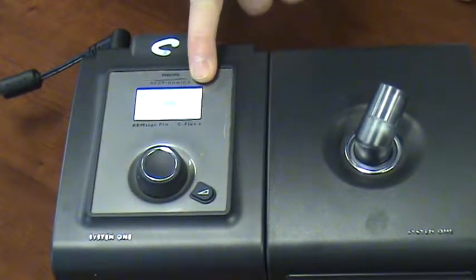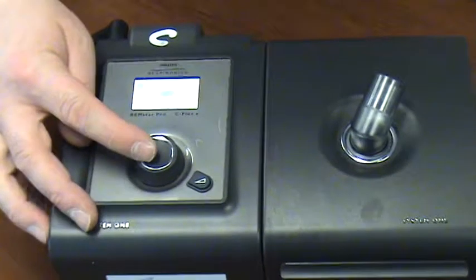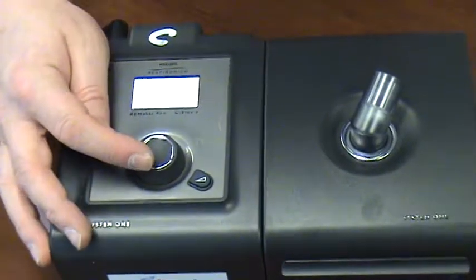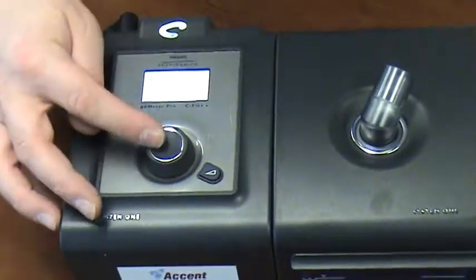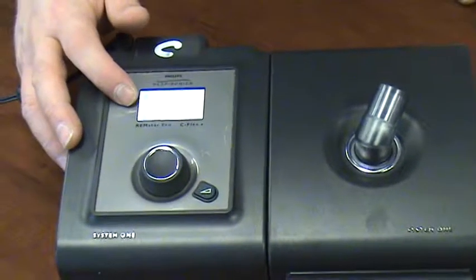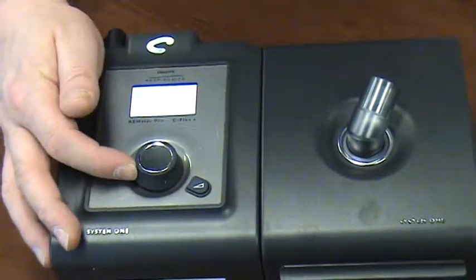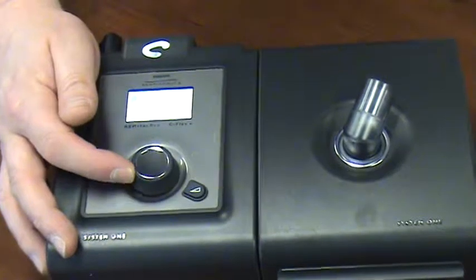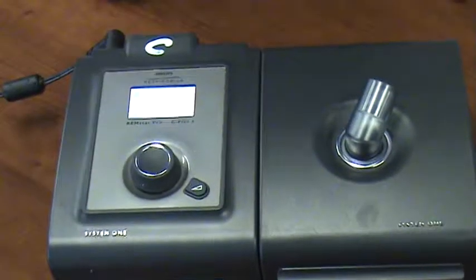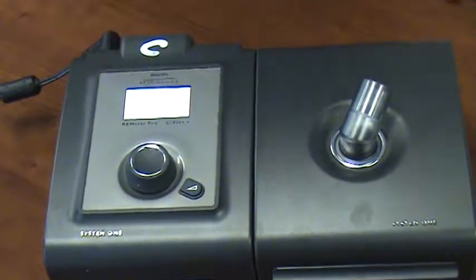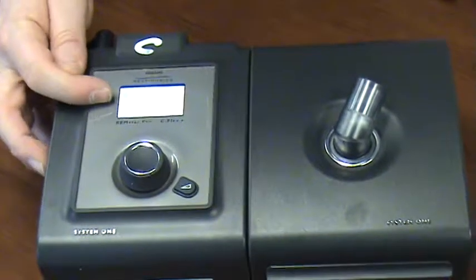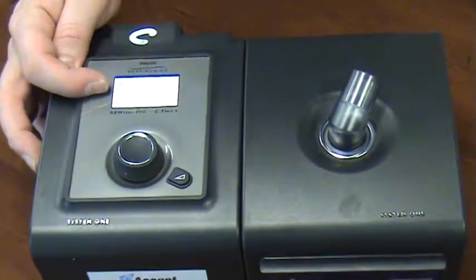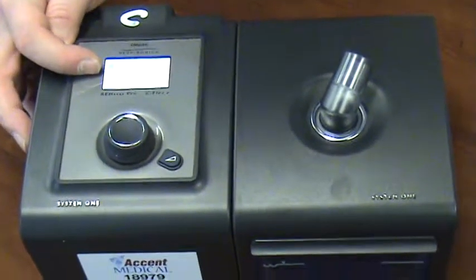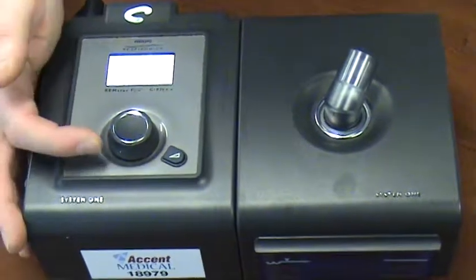But some units may say CPAP versus auto, okay? So we don't want to really worry about the mode. CPAP pressure, come down here, press the dial to select CPAP pressure, and by turning the dial, as you can see, I can adjust the pressure up or down. I'll press the dial again to save my setting. For a BiPAP, the only difference would be there would be a high and low setting. There's 2 settings for the BiPAP versus 1 for the CPAP.